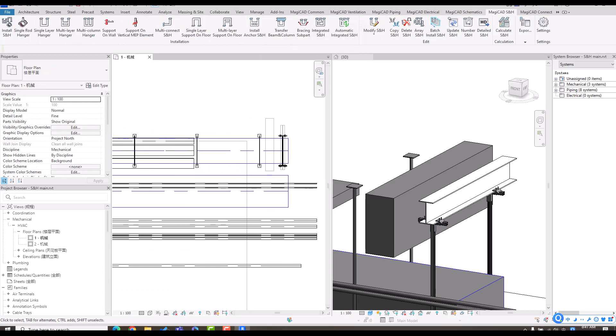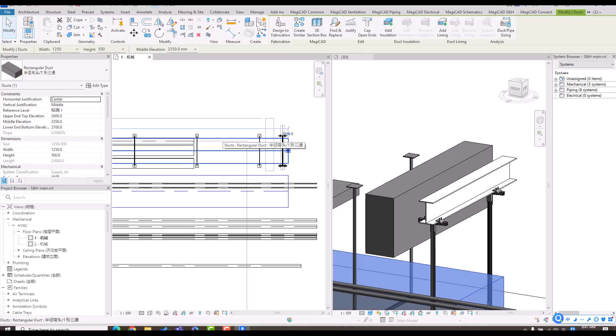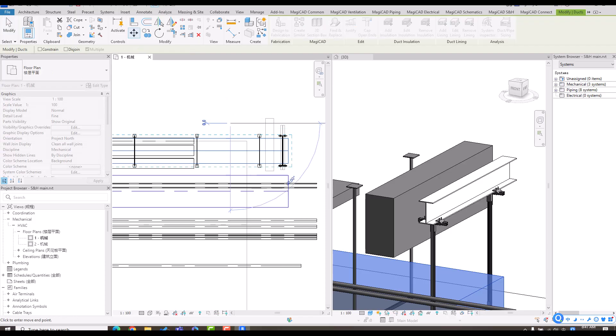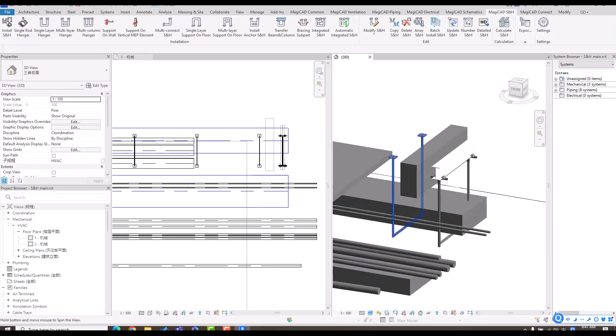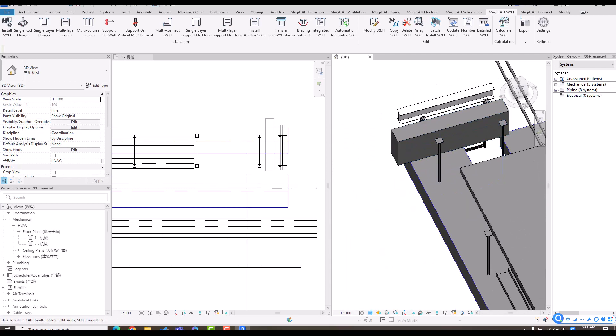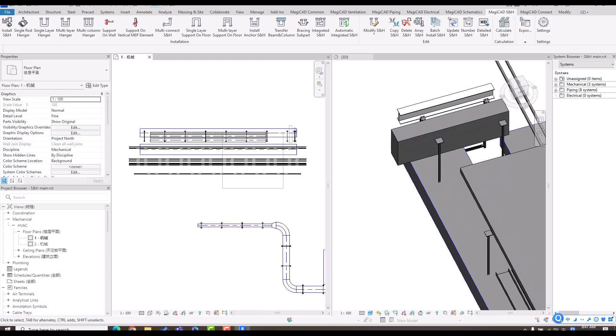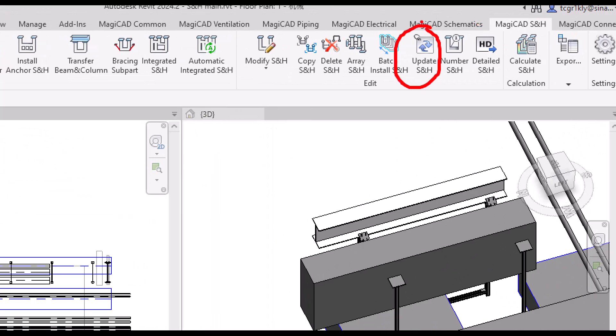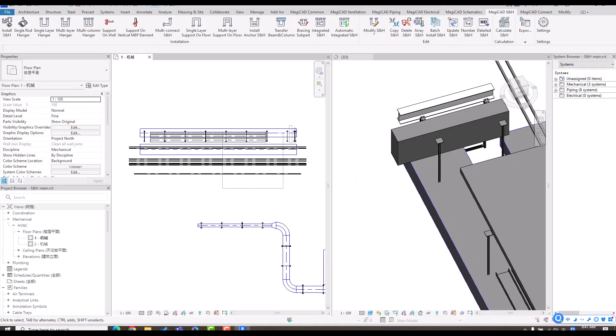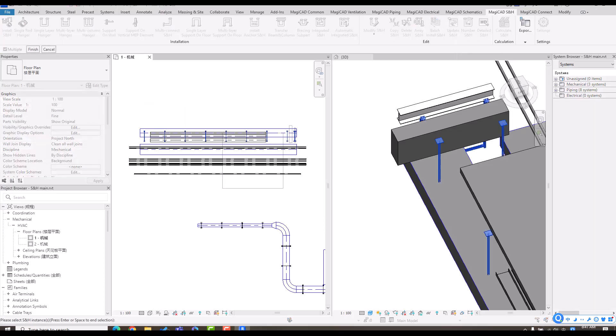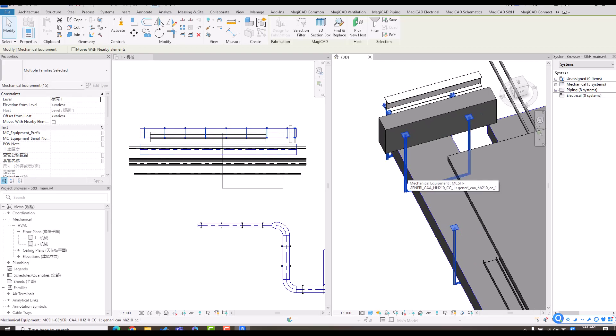Those are functions for installation and editing. If you have changes — whether from the architecture, structure, or MEP side — for example, if I move the duct to another place, the support hanger instance will go through the element and be incorrect. We provide an update function to update those instances according to the latest segment — no matter the size, elevation, or position. I use the update function, select the instance, finish, wait a few seconds, and we can update it to the latest state.